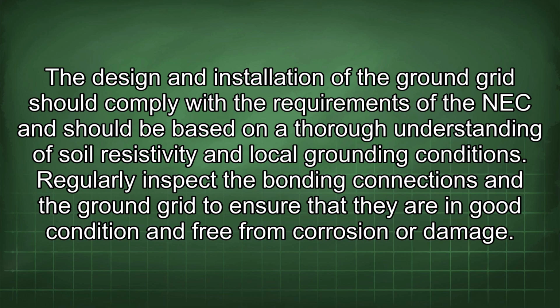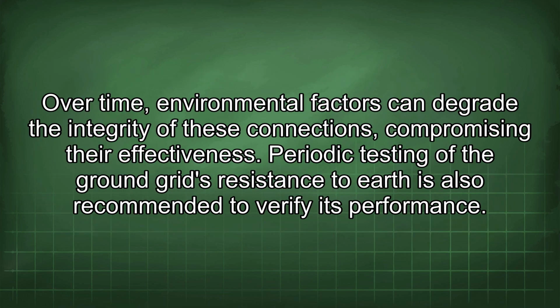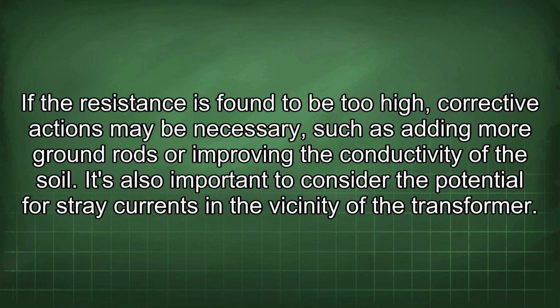Regularly inspect the bonding connections and the ground grid to ensure that they are in good condition and free from corrosion or damage. Over time, environmental factors can degrade the integrity of these connections, compromising their effectiveness. Periodic testing of the ground grid's resistance to earth is also recommended to verify its performance. If the resistance is found to be too high, corrective actions may be necessary, such as adding more ground rods or improving the conductivity of the soil.